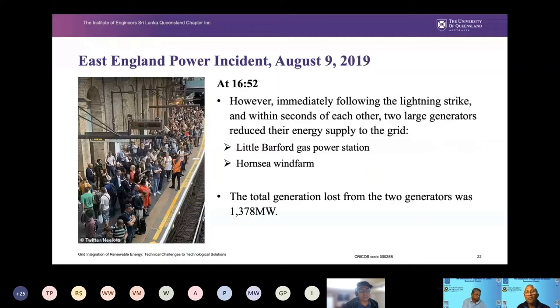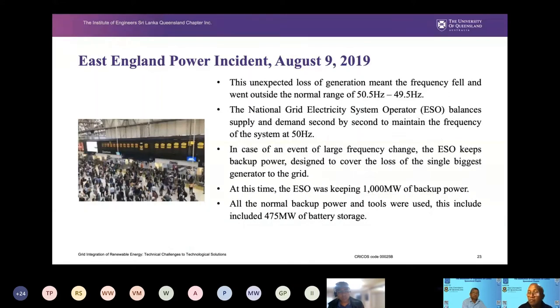So at about 4:52, immediately following the lightning strike, and within a few seconds, two large wind farms, and also a gas-fired power plant, had to be stopped from generating. So this created a vacuum of generation. The total generation lost was about 1,400, and that 1,400 generation created a big vacuum and allowed the frequency to swing.